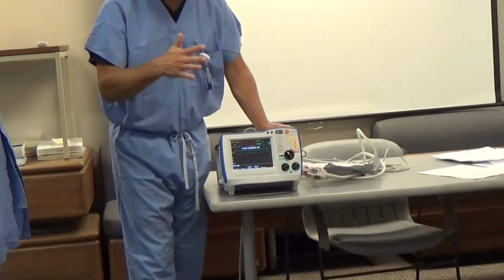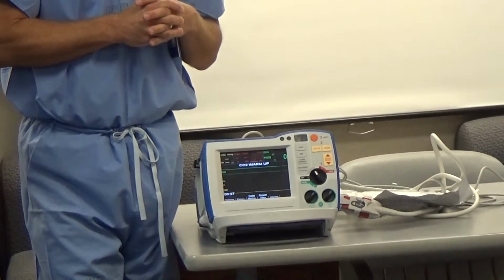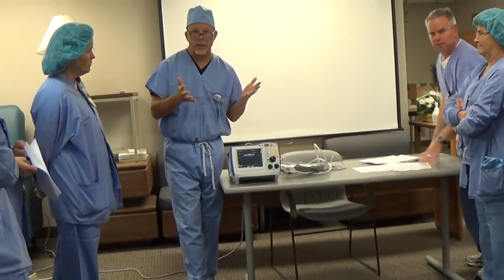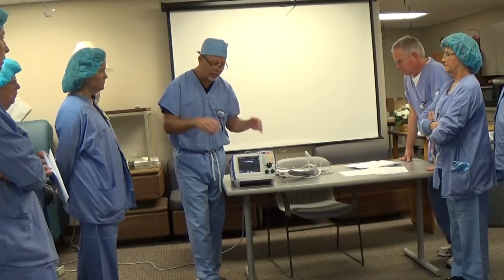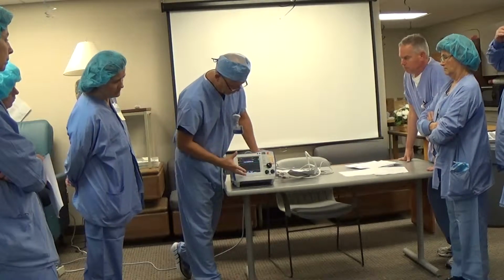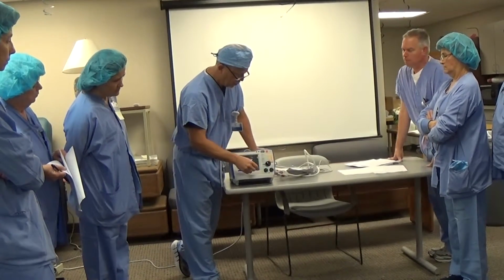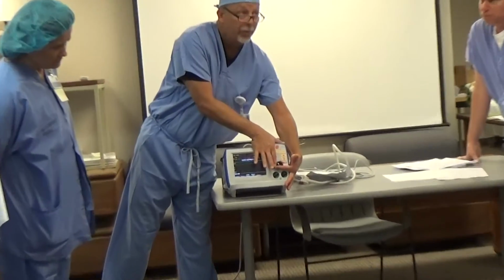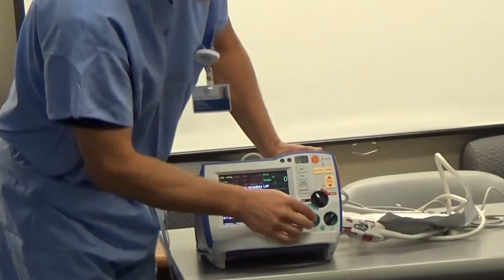But, okay, back to our scenario. So if we hook this person up, we're going to go through some rhythms in a minute, and they're in ventricular fibrillation, which is just a squiggly little line. What do we do? Shock them. So what we would do is, you see your off button, your monitor, which is where we're on, is just for assessing. You have the pacer down here in green, and we'll talk about that in a minute. But your defibrillator mode is all up here in the orange. Unless I'm colorblind and that's red. Is it red? It's both.